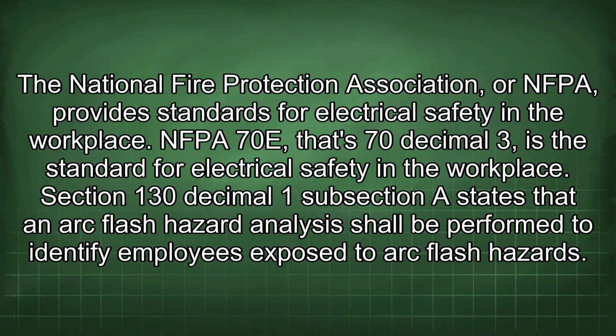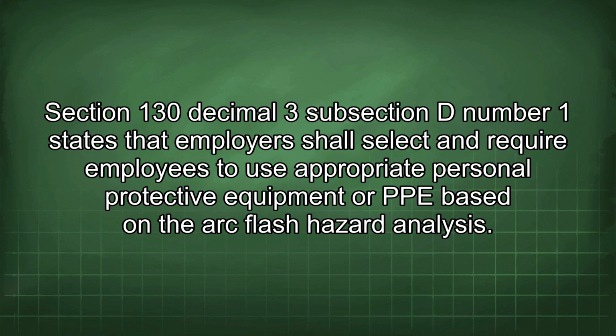The National Fire Protection Association, or NFPA, provides standards for electrical safety in the workplace. NFPA 70E, that's 70.3 is the standard for electrical safety in the workplace. Section 130.1 states that an arc flash hazard analysis shall be performed to identify employees exposed to arc flash hazards. Section 130.3 subsection D number 1 states that employers shall select and require employees to use appropriate personal protective equipment, or PPE, based on the arc flash hazard analysis.